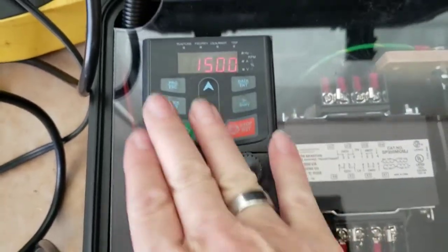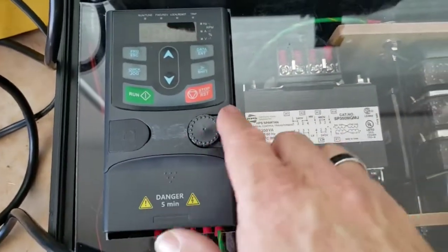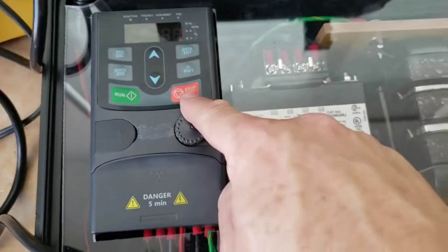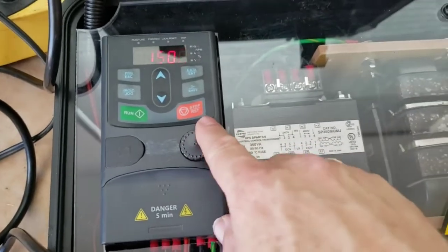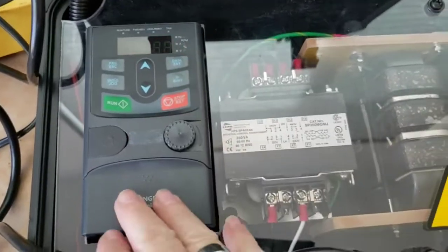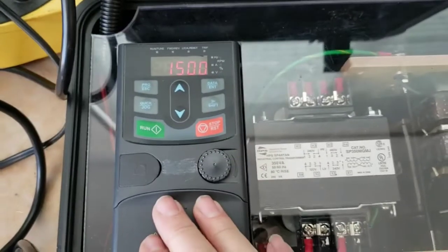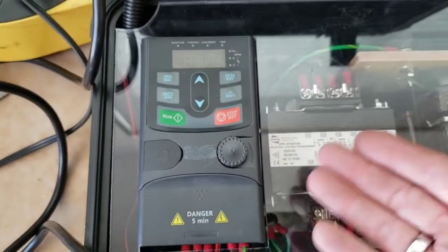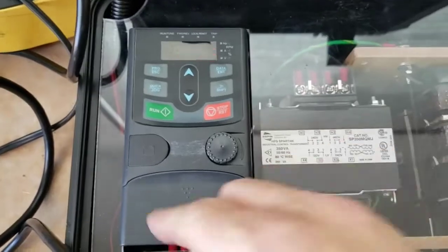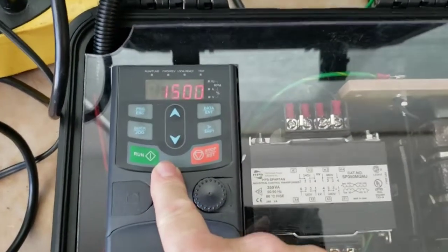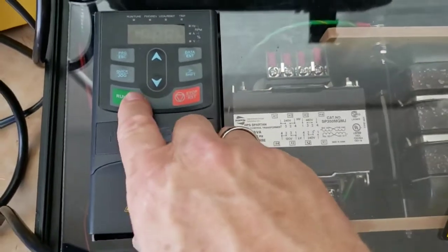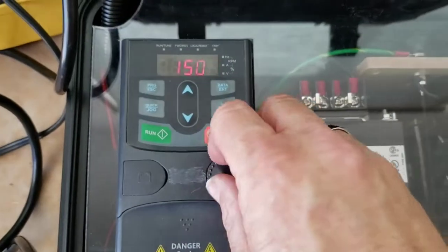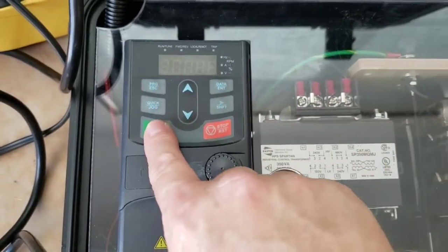If it starts reacting and you know before it completes its sweep that it's failing, go ahead and hit the stop or the reset button. There's no need to let it finish. You just perhaps do more damage to the cell if it is salvageable, and there's no sense in putting an extra load on the test box if you know for a fact that it's failing before you even get through the full test. So we're going to do a sweep test. Let's hit run, and then we'll watch it go through the full sweep, and we'll listen to it.